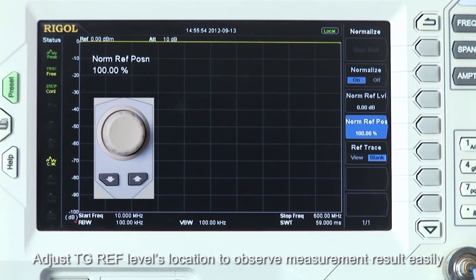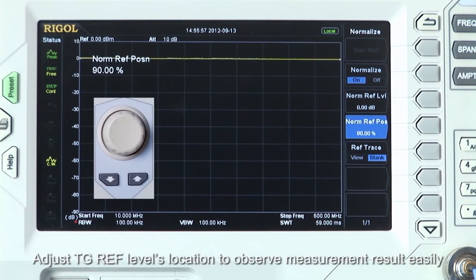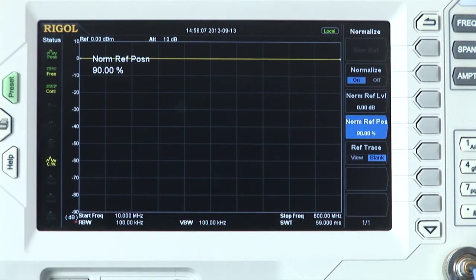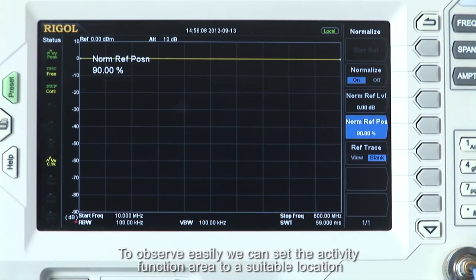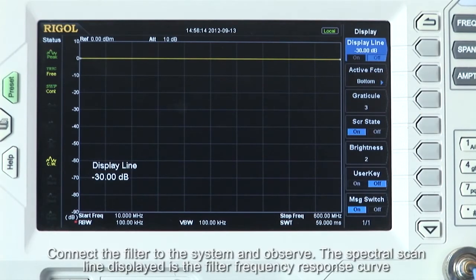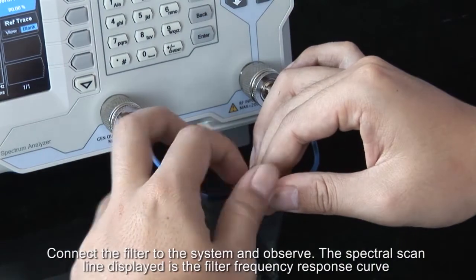Adjust the tracking generator reference level location to observe the measurement results easily. Note: the tracking generator reference level only changes the location of the signal displayed — it does not change the spectrum analyzer reference level. To observe easily, we can set the activity function area to a suitable location. Connect the filter to the system and observe. The spectral scan line displayed is the filter frequency response curve.